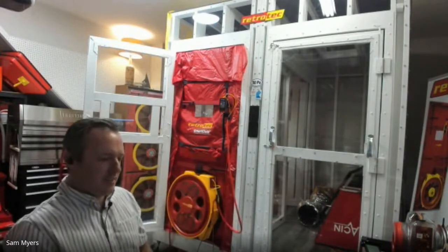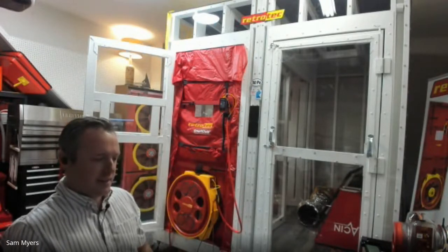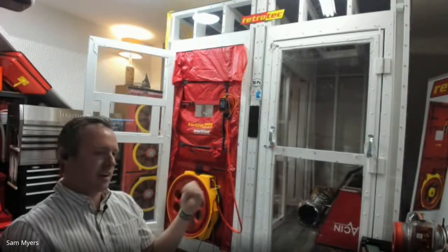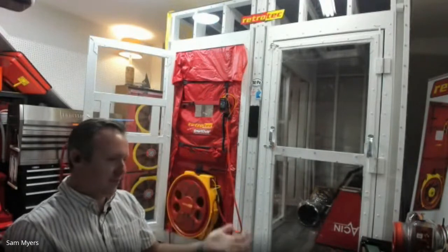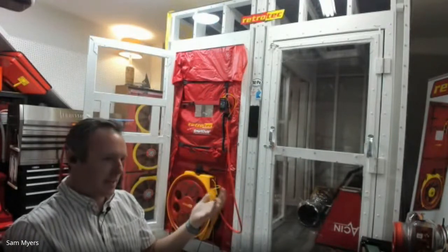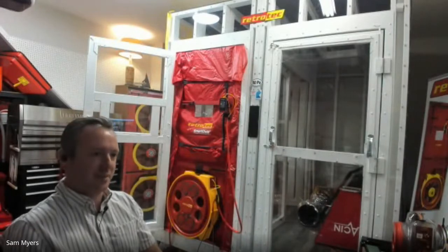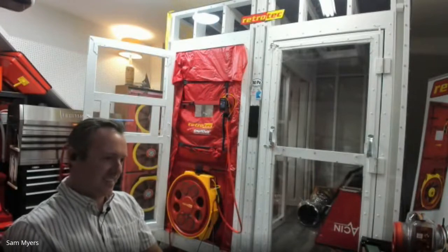And what I like to do, once I've checked all that and it looks good, I'll run the fan to maybe half pressure, so go to 25 pascals, and just walk around. Check that fireplace out, see if anything smells weird, is anything damp coming in. Is there a P-trap that's open? If there's a P-trap and there's water in it, you'll know it pretty fast if you're depressurizing. Yeah, done that before.